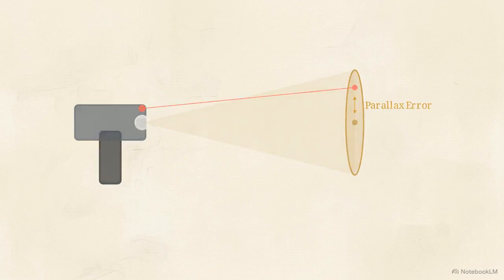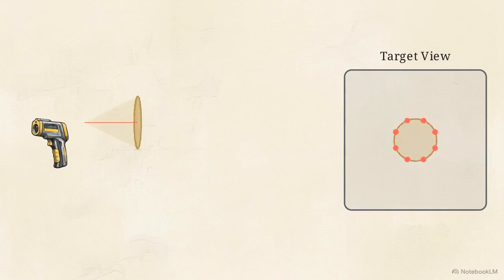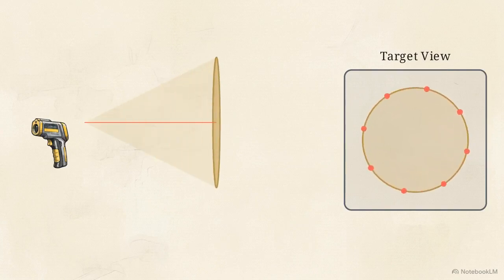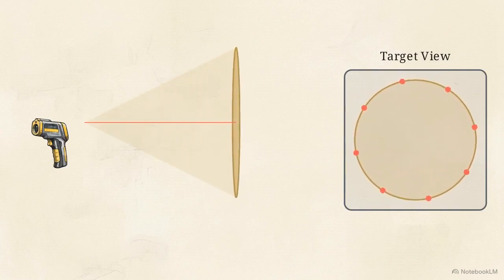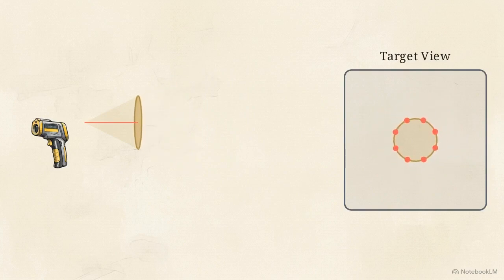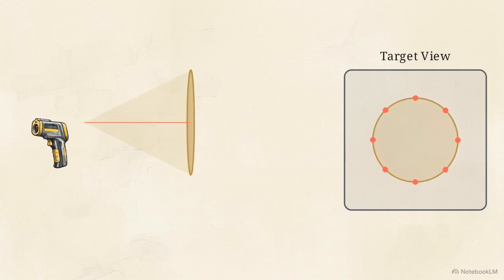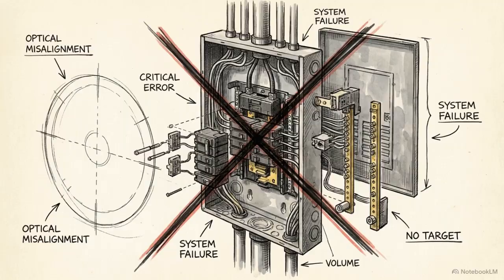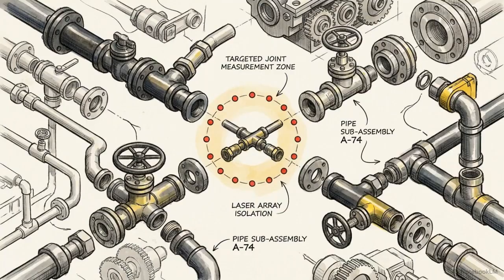Standard off-axis lasers create parallax error, missing the sensor's true center. The MX6 uses a coaxial system projecting down the optical center. Its 635 nanometer laser circle expands and rotates with distance, showing the precise boundary of the averaging zone. If the optical boundary isn't perfectly matched to the physical target, the thermal data will be false. By eliminating parallax error entirely, the coaxial optics ensure the digital photograph captures the exact area the sensor analyzed.